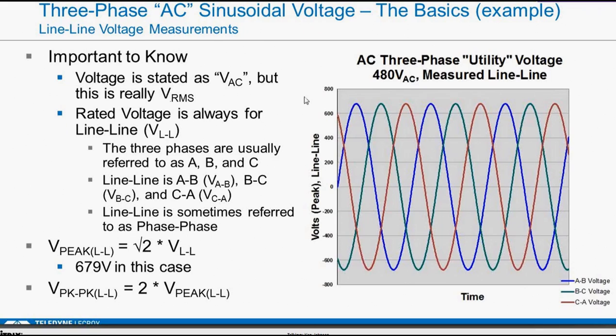Okay, so as we look at the voltages, where it gets a little tricky, this is still, in the U.S., called a 480-volt AC system. In Europe, 380 volts or 400 volts, right? But that voltage level, quoted volt AC, is a line-to-line voltage. It's not a line-to-neutral voltage. Therefore, the math is a little bit different.